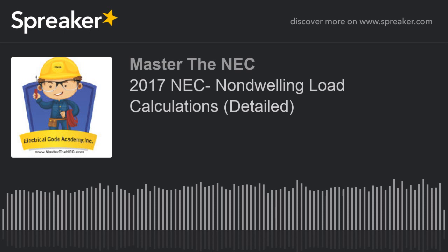Under 220.61, you'll see that a 70% demand factor is permitted for that portion of the unbalanced load that's above 200 amperes. So let's say I've got 300 amperes of neutral load, and that's what I've calculated based on all of my connections that utilize a neutral conductor. Or in our case, when we say neutral is used as a grounded conductor. We're going to keep them synonymous for the purpose of this calculation, so we know that they are mutually the same.